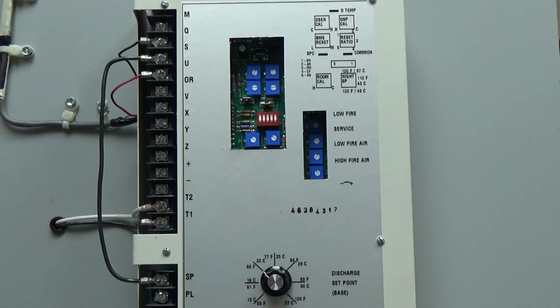The GTRAC2 has several different set point options, from standalone base set point, remote panel set point, to 0 to 10 VDC reset, room reset, and even ambient reset. The set point calibration that we will cover is the standalone base set point dial on the GTRAC2 control board. To know what type of set point is controlling your unit, you should refer to the unit function page installed in the unit control cabinet.